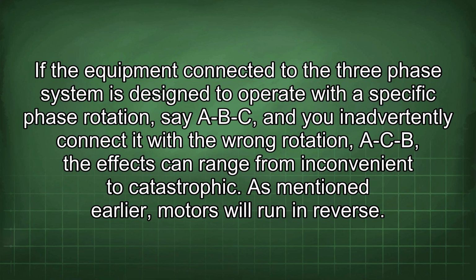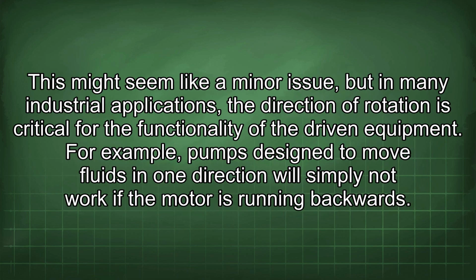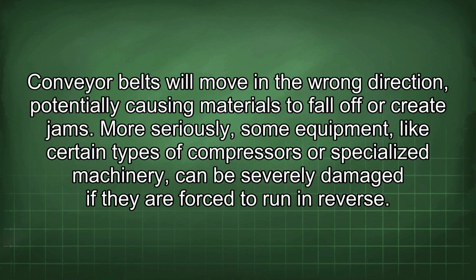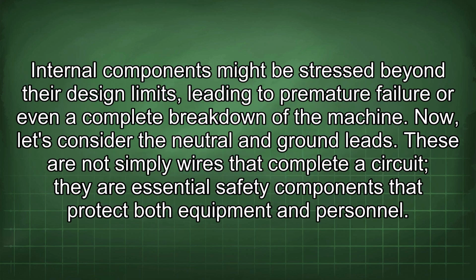As mentioned earlier, motors will run in reverse. This might seem like a minor issue, but in many industrial applications, the direction of rotation is critical for the functionality of the driven equipment. For example, pumps designed to move fluids in one direction will simply not work if the motor is running backwards. Conveyor belts will move in the wrong direction, potentially causing materials to fall off or create jams. More seriously, some equipment, like certain types of compressors or specialized machinery, can be severely damaged if they are forced to run in reverse. Internal components might be stressed beyond their design limits, leading to premature failure or even a complete breakdown of the machine.